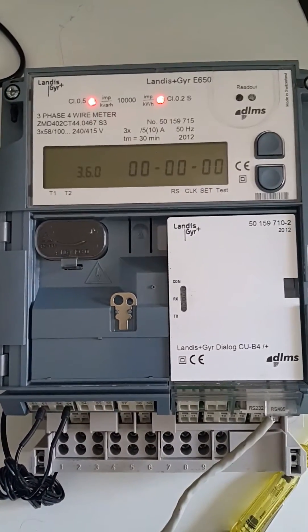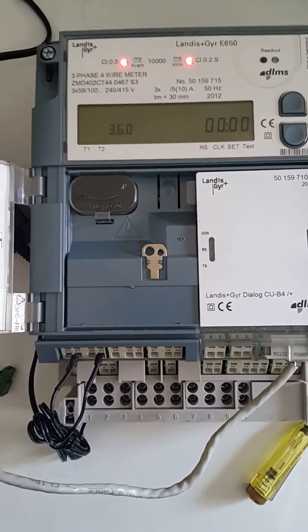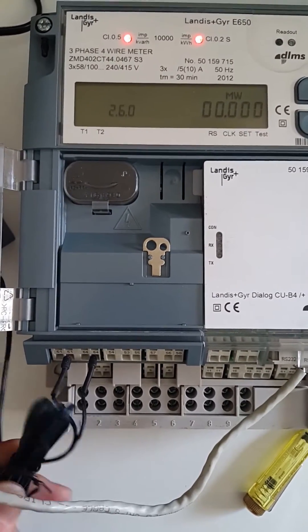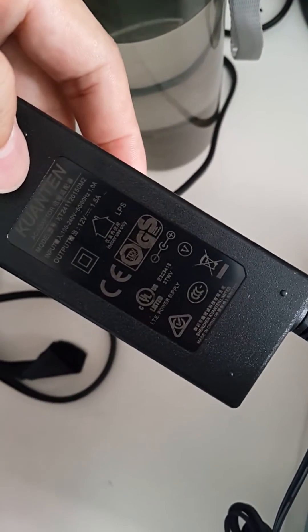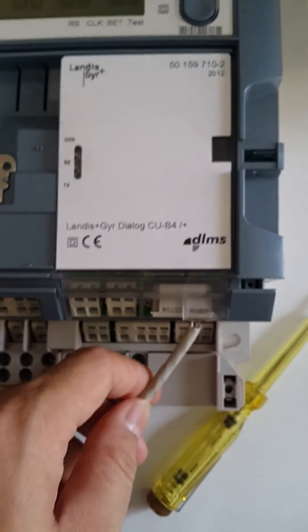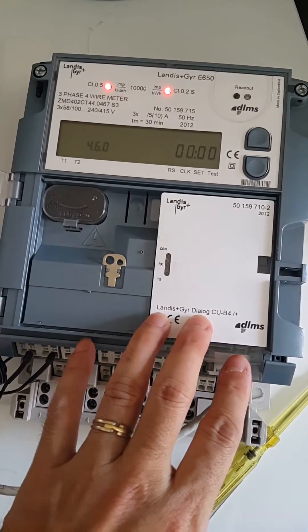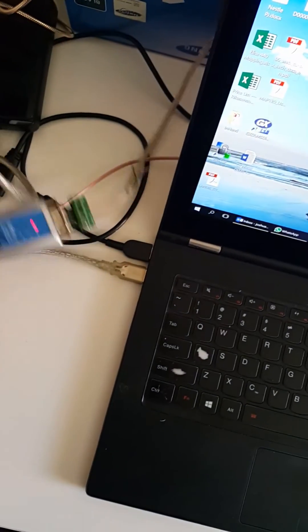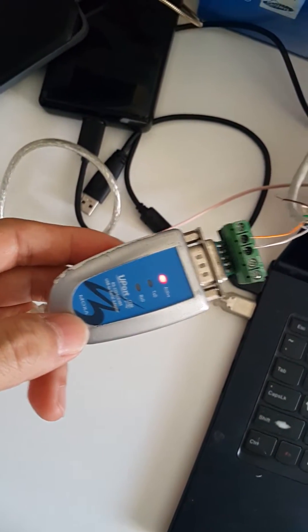This is the Landis+Gyr E650 meter being powered up right now. I'm using a 12-volt DC power supply plugged in according to the manual. This is the RS-485 communication module — without the power supply, the communication module is not going to work. This is connected to my laptop through a USB to RS-485 converter; in this case I'm using UPort 1150.